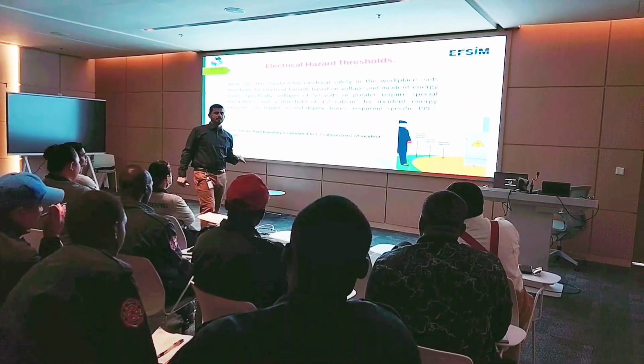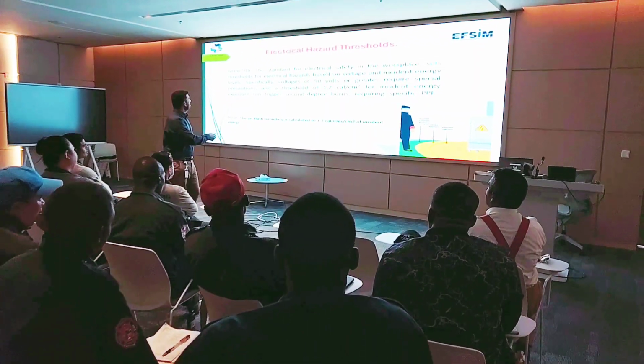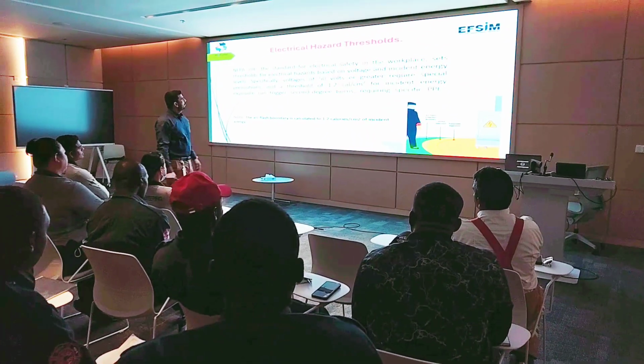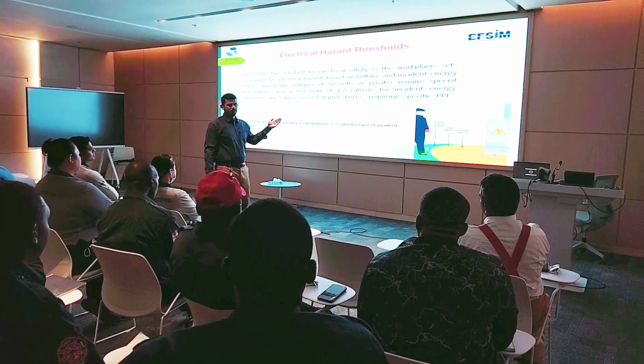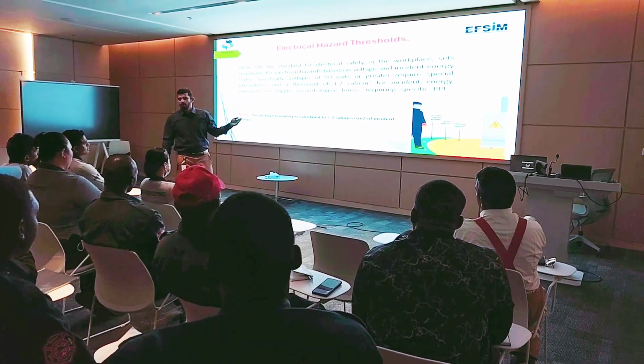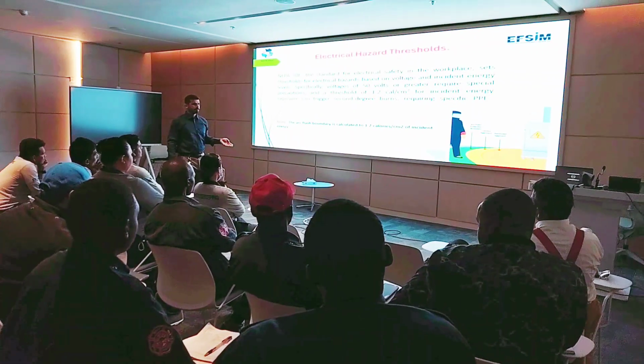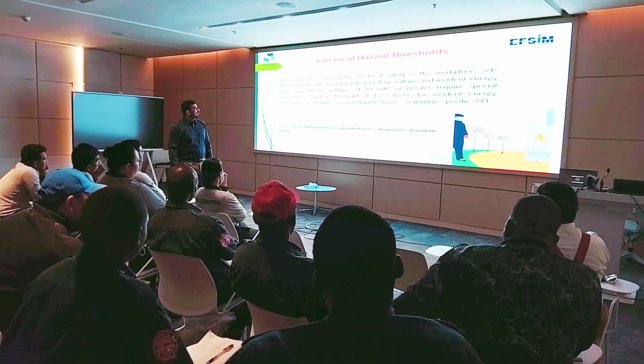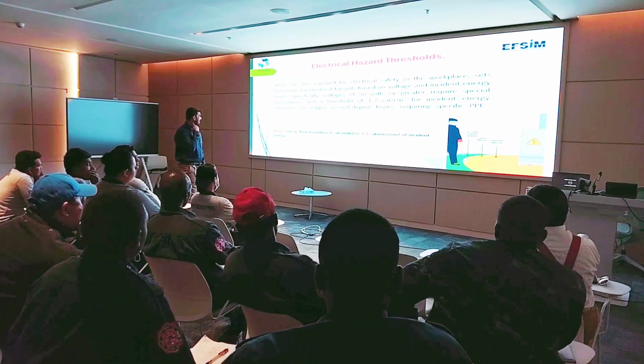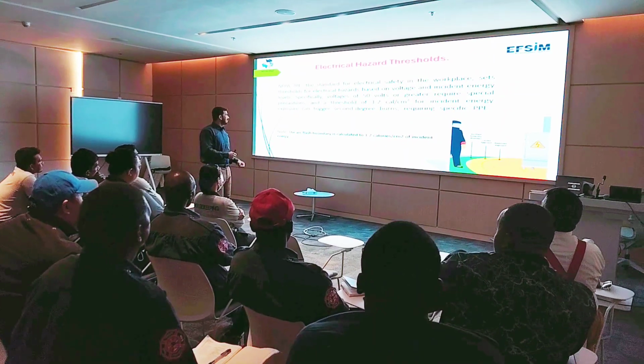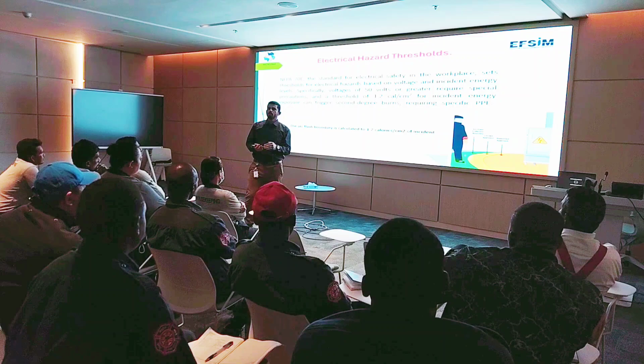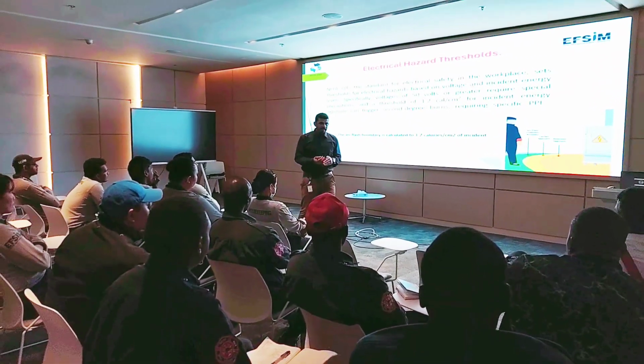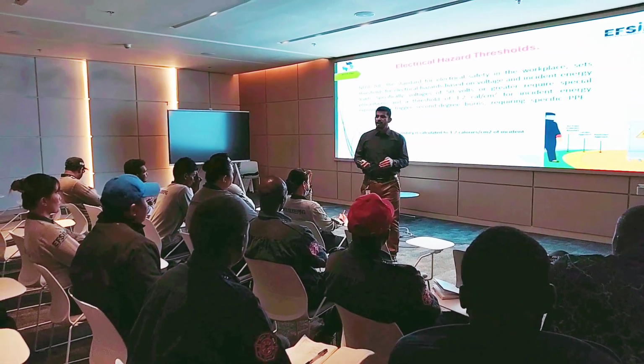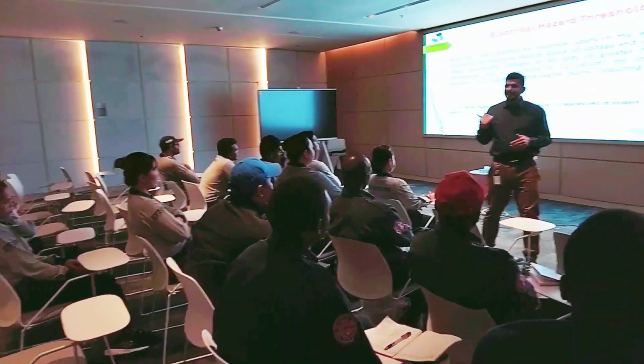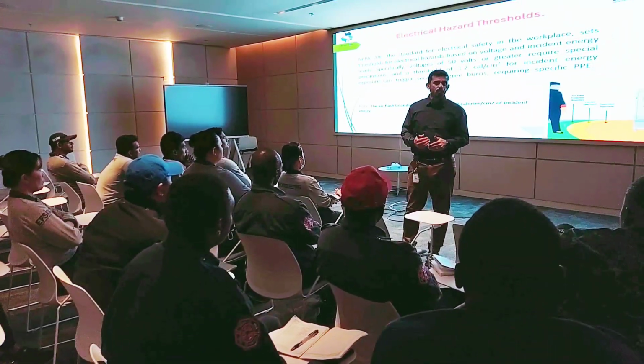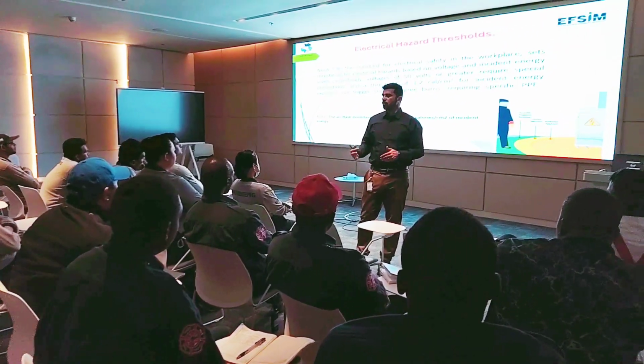The threshold limit is about 1.2 calories per square centimeter. It's a standard used to check the threshold hazard for electricity. The standard for electrical safety in the workplace sets thresholds for electrical hazards based on the voltage and incident energy level, as I already told you. That's why in most workplaces we choose equipment utilized for DC, meaning less than 50 volts, not 220 volts.